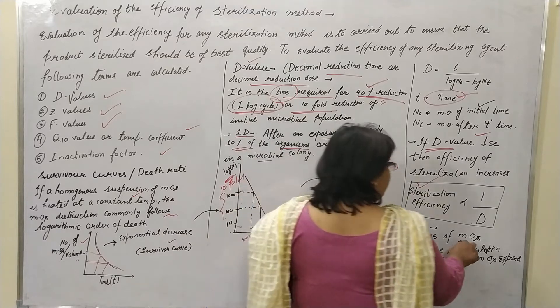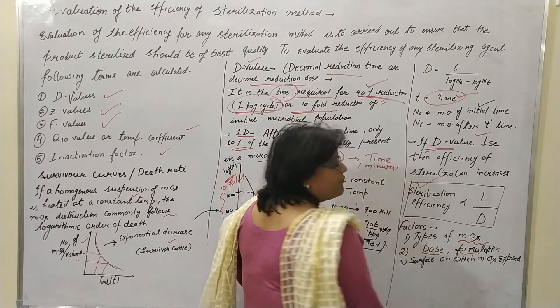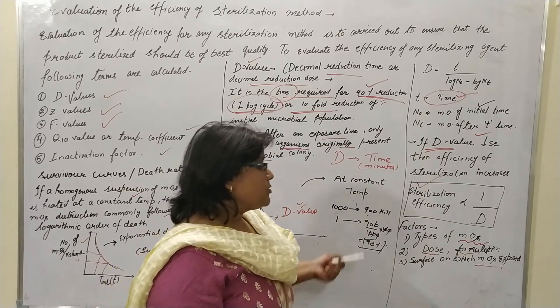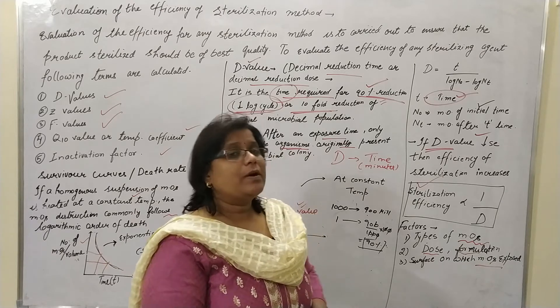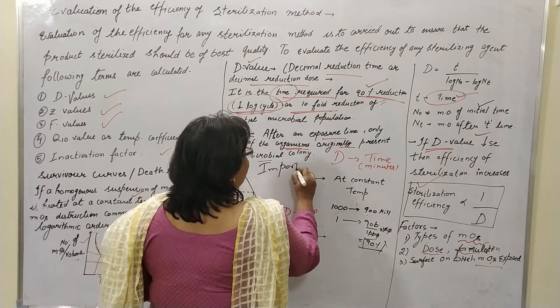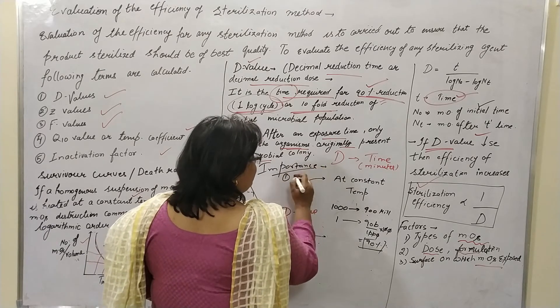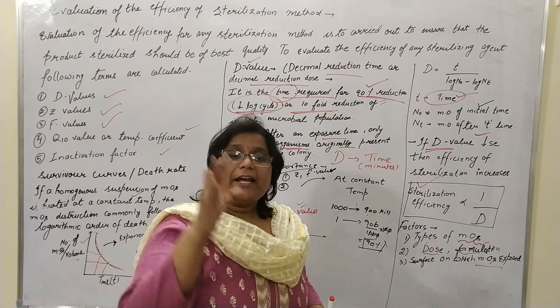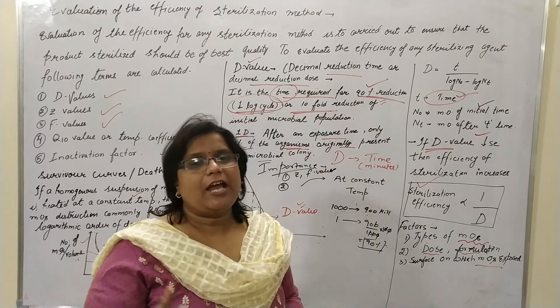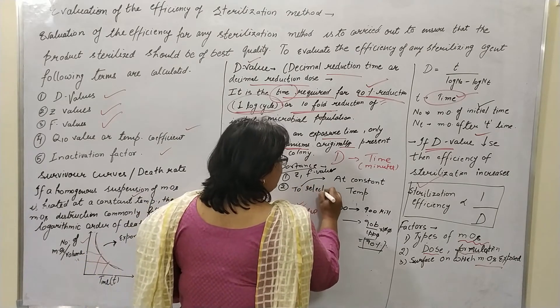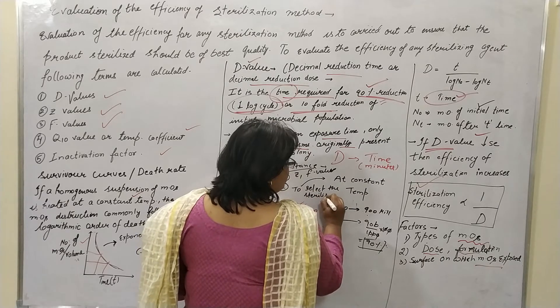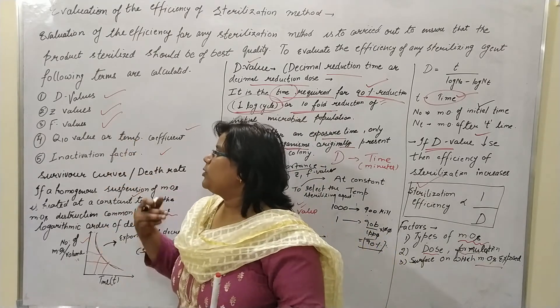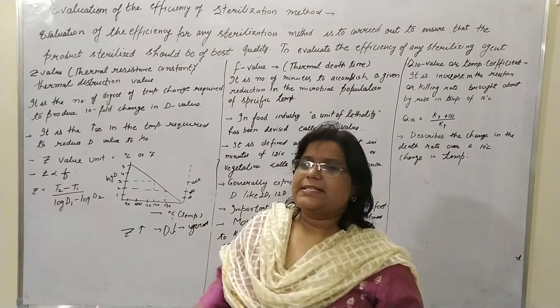The formula is: D equals t divided by log(N0) minus log(N), where t is the time of sterilizing agent exposure and N is the microorganism count. The unit of D is minutes. With the help of the D value, we can determine the sterilization efficiency. If the D value is less, the time required is less and the sterilizing agent is more efficient.